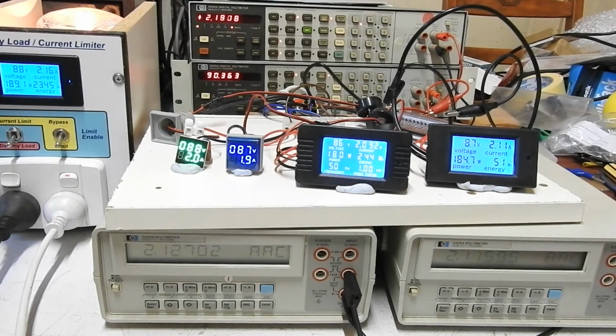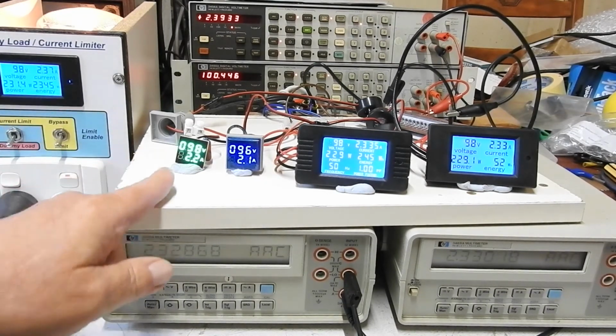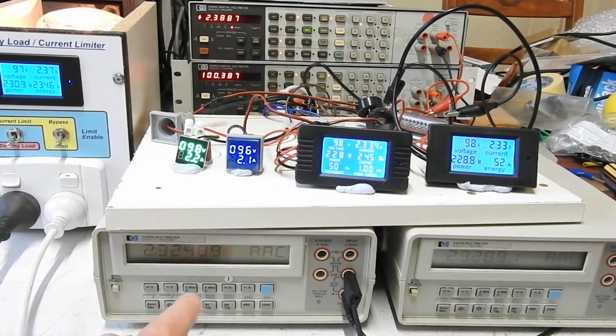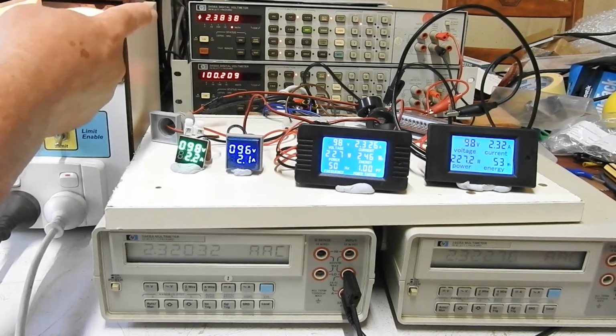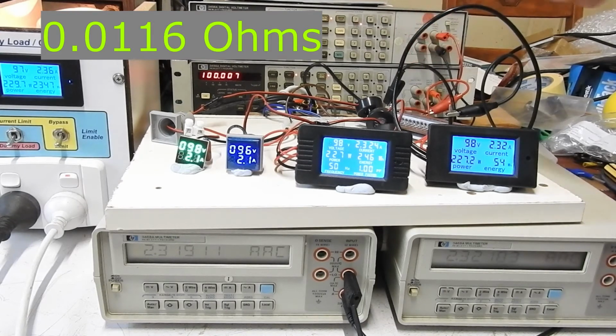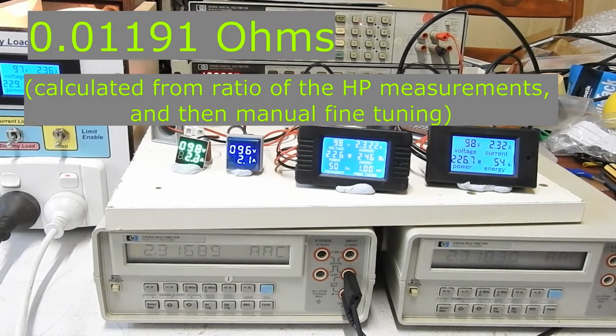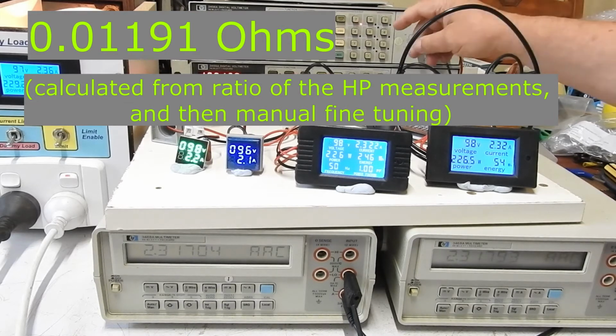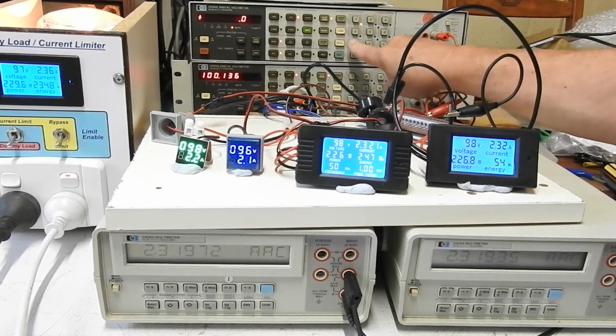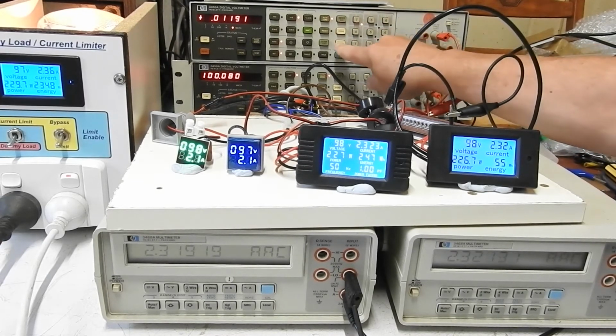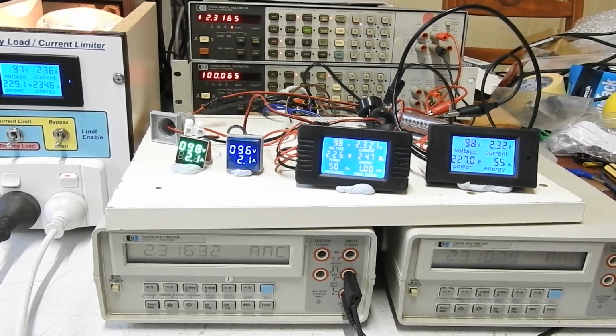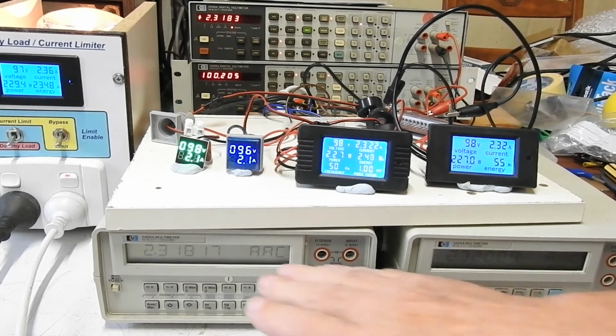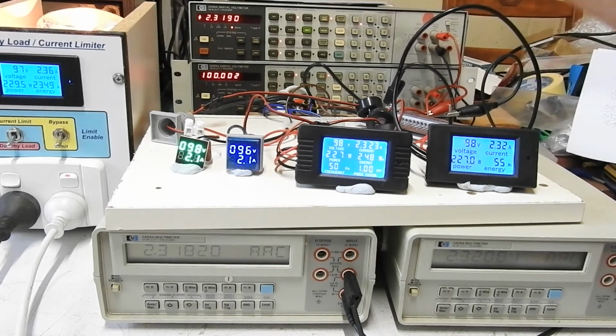Let's take it to 100 volts. 100 volts, we got 2.37 amps, 2.2, 2.1, 2.33, 2.33, 2.32, 2.32. And again, my meter up the top is too high. So what I can do is change the number that I've entered into this thing for the resistance of that. If I change it to 11.91 milliohms instead of 11.6, so 0.01191, still there. That's more like it. They agree more with the HP. So assuming these two HPs are accurate, now that's been adjusted to meet these same current as these two.